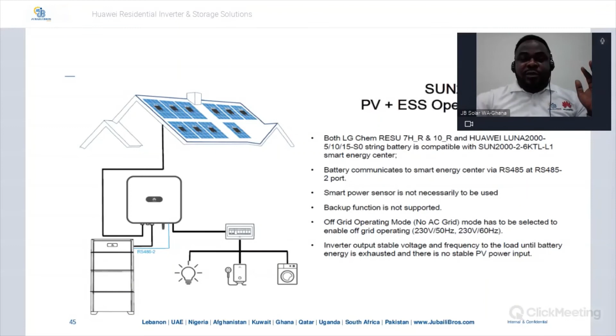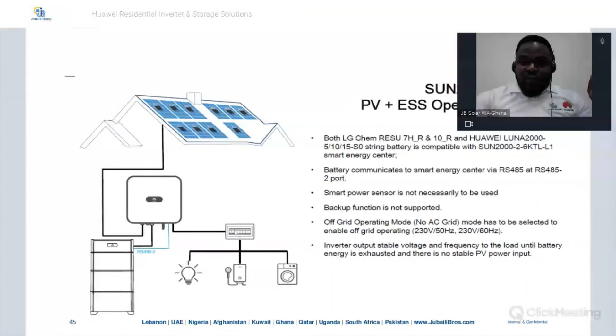Another good thing about this: please take note, the system works only with inverters that are single phase. Three-phase Huawei inverters cannot operate in a completely off-grid mode. It's only the single-phase inverters that can do that. So another point for you to take note.